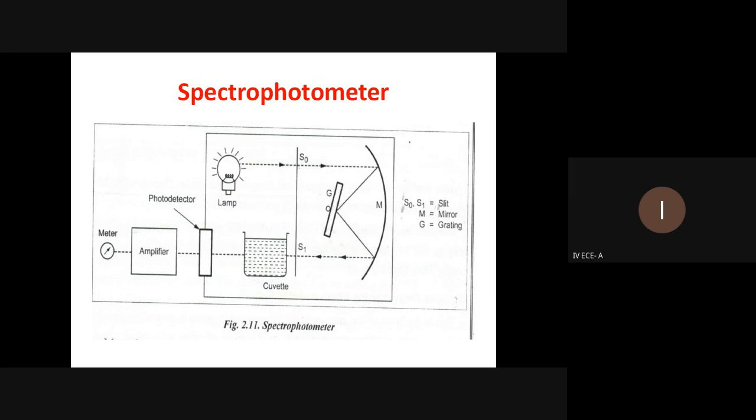If a single detector such as a photomultiplier tube or photodiode is used, the grating can be scanned stepwise so that the detector can measure the light intensity at each wavelength. An array of detectors such as charge coupled devices or photodiode arrays can also be used. In such a system, the grating is fixed and the intensity of each wavelength of light is measured by a different detector in the array.